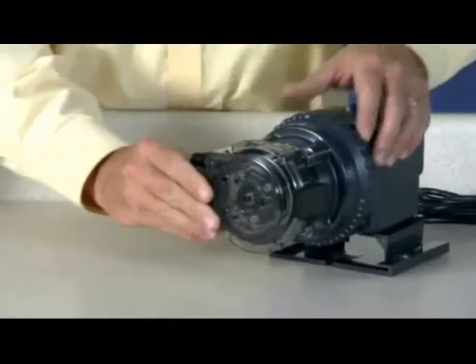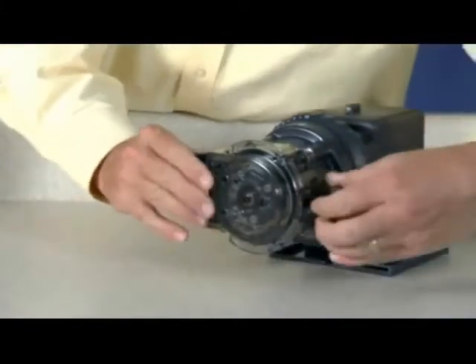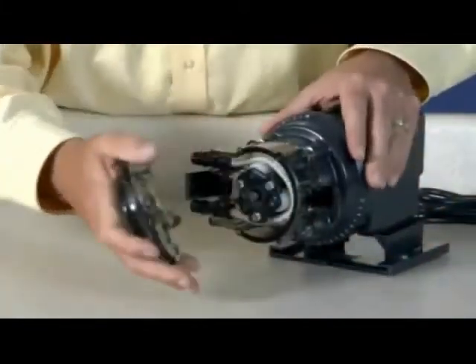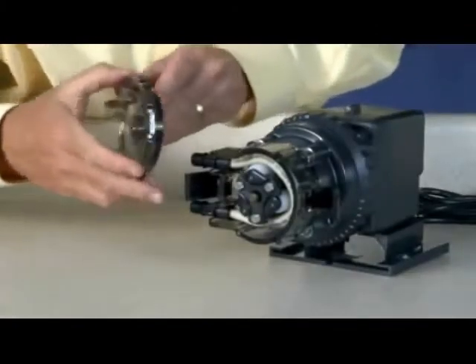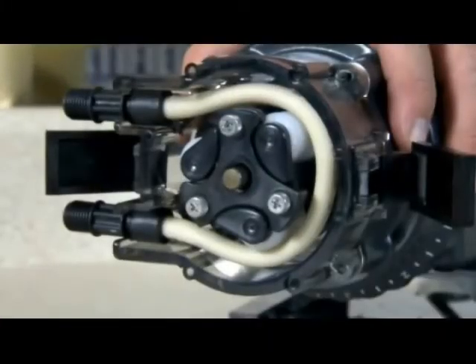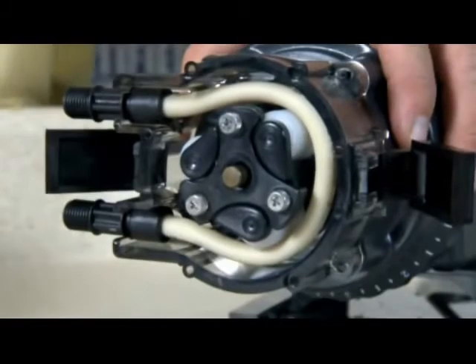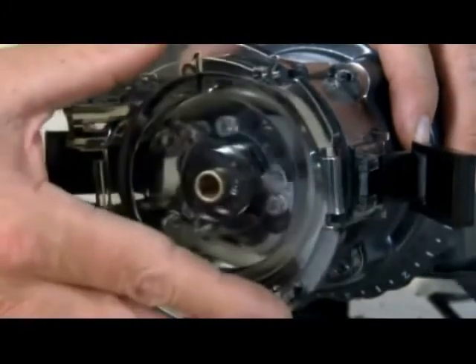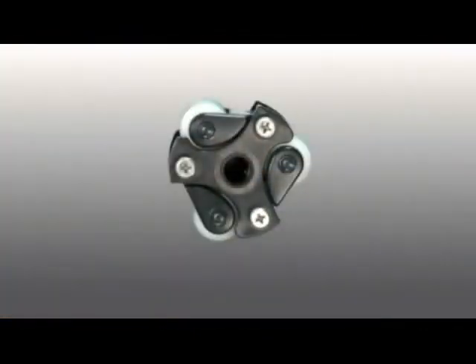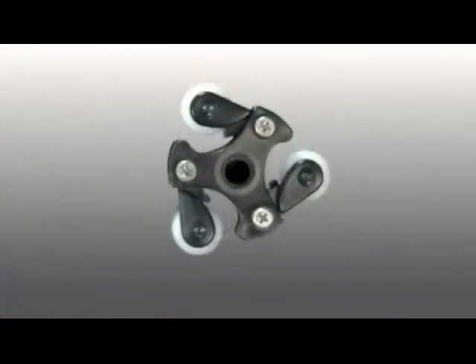Remove the tube housing cover and flip to use as a tool to expand the roller assembly. Align the center of the inverted cover with the center of the roller assembly so that the 3 holes on the face of the cover align with the 3 knurled lugs on the roller assembly. Position the cover feet near the bottom. The roller assembly needs to be expanded so the tube is pressed against the tube housing wall.